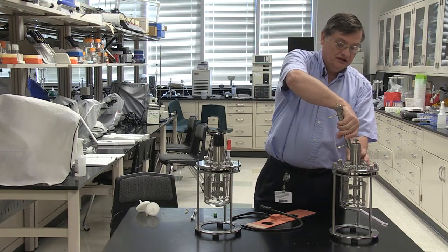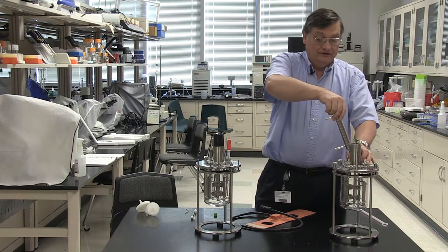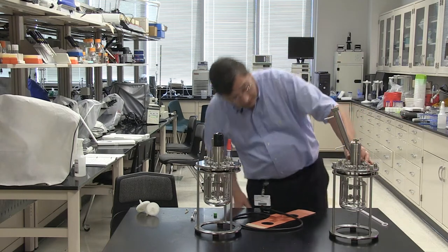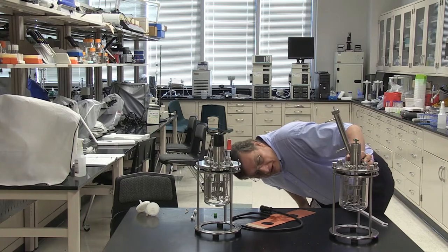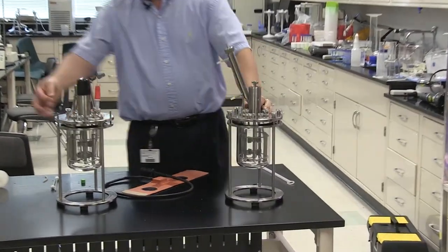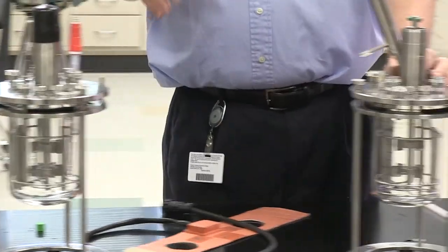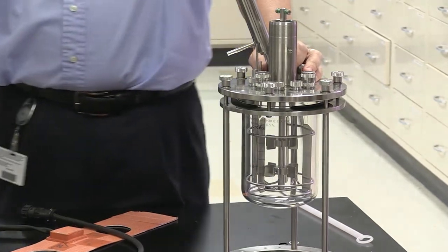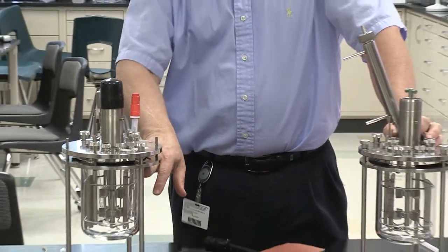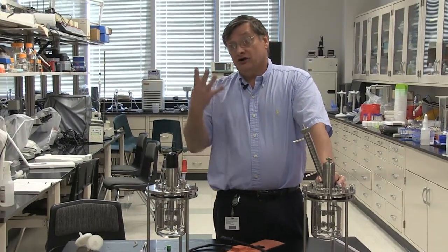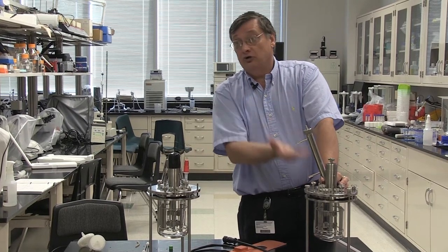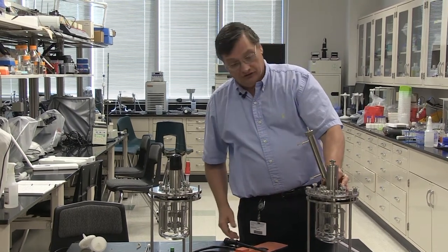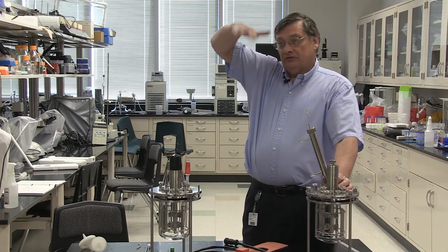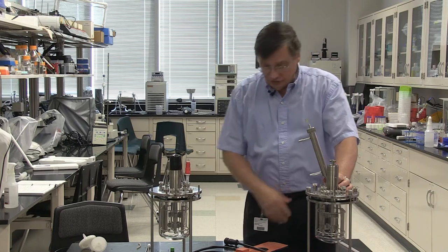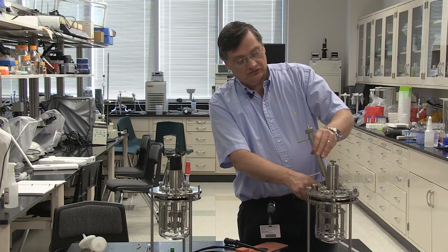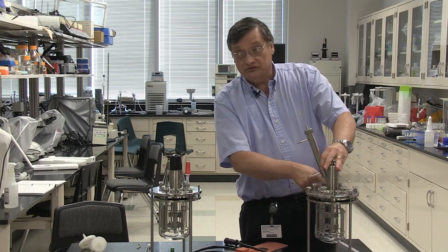And then you can assemble it on there. Now, my preference is when you're putting it on there to look through and make sure that it's going all the way through the head plate and the clamp plate, but not much further. If you push it all the way down, it gets close to the liquid level, particularly if you happen to have a whole liter in here. Then it's going to bubble a little bit with the air coming in, and those bubbles are going to try to go up the condenser and create moisture in there. So my preference is to have them through the plates, but just enough so that you see them through the plate. And then you can adjust the position with the three set screws.